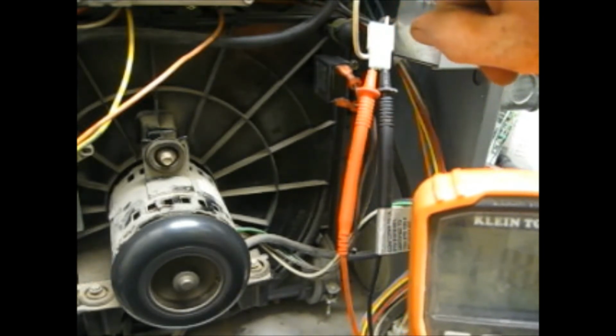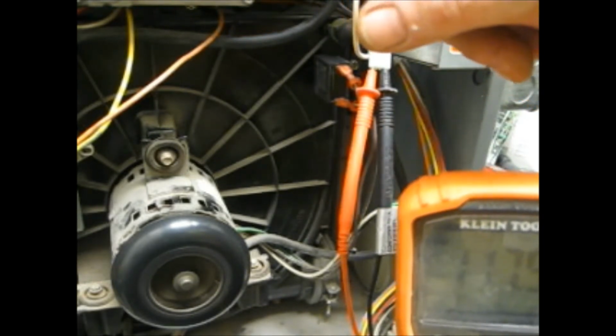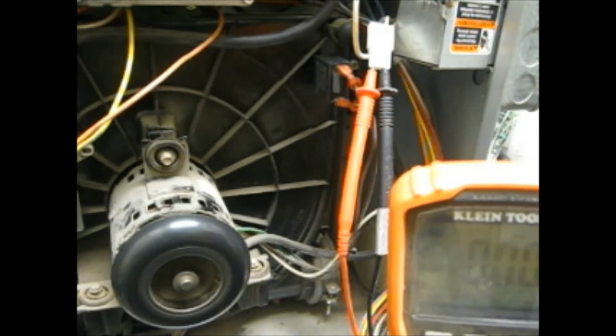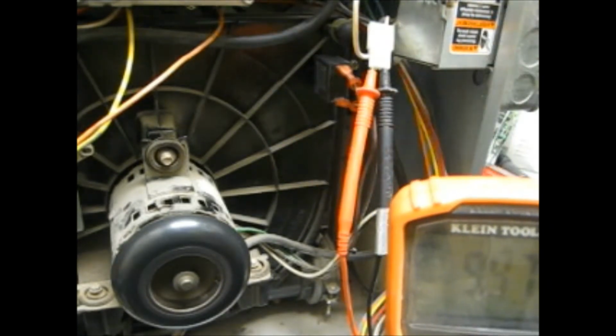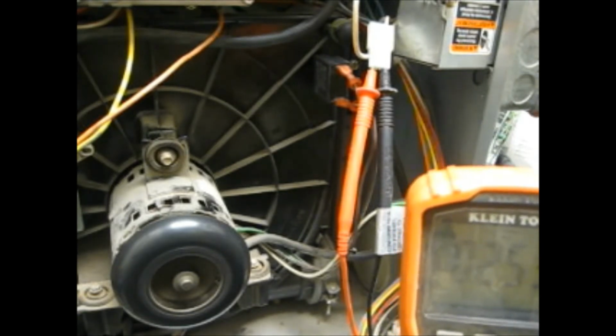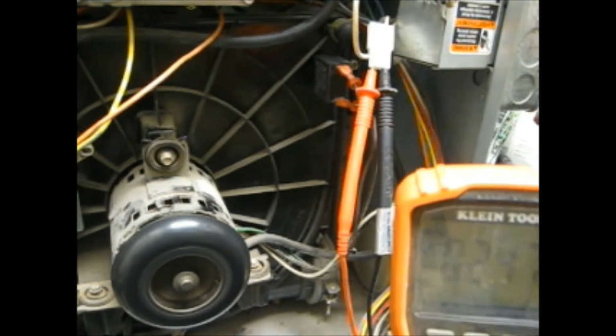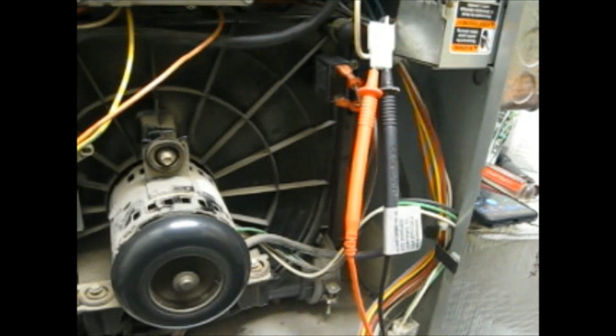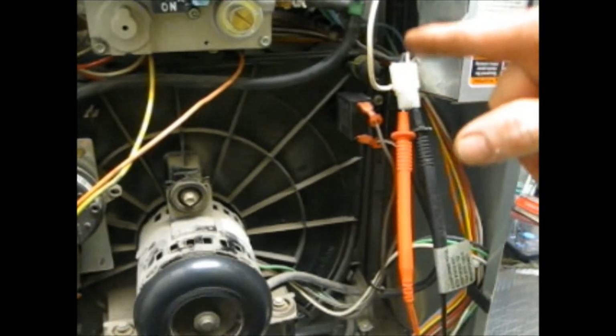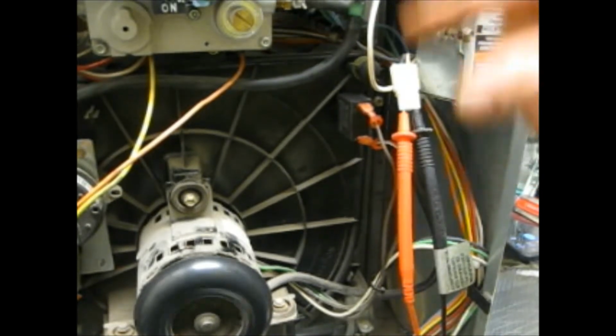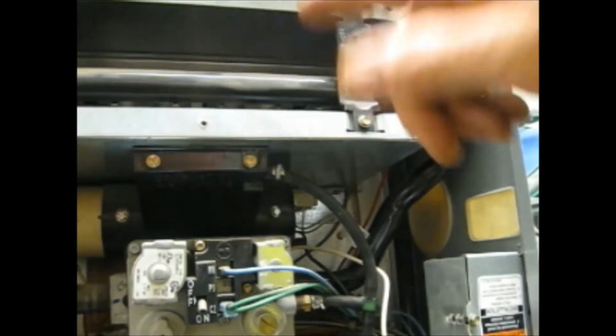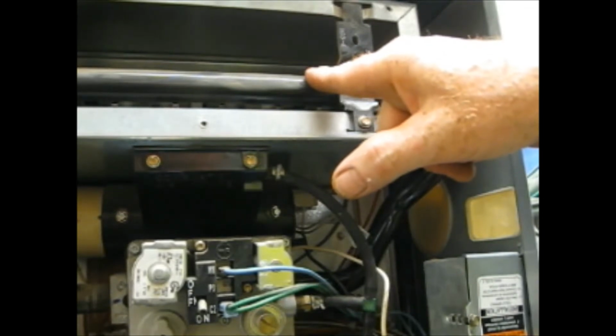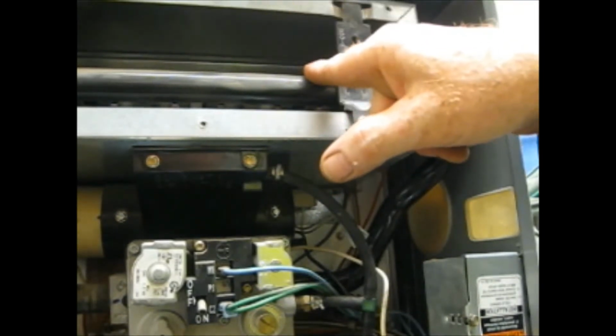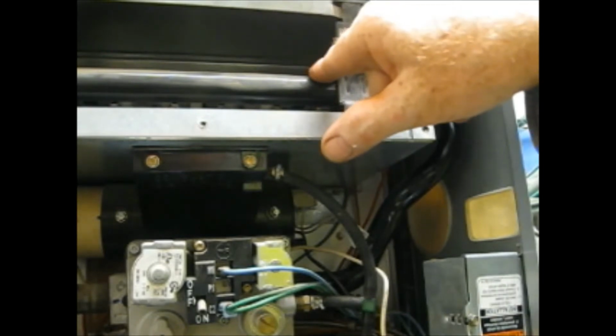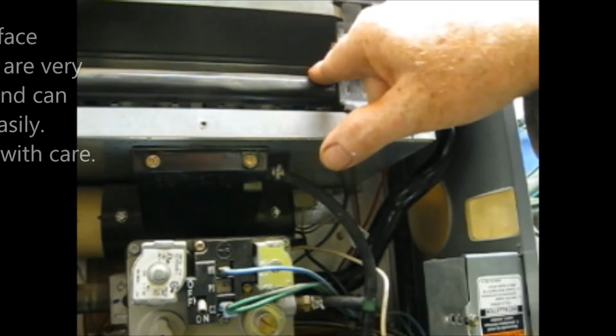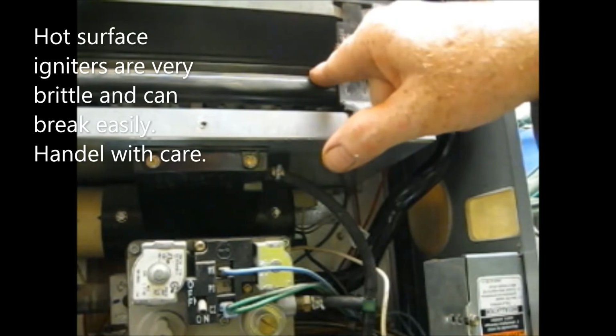the igniter. Now what's going to happen is it's going to attempt to light, but because it's not going to sense any flame, it's going to shut everything down. And there we go. Everything has been shut down because there wasn't a flame up in our chamber. If this were to happen to you where we get 120 volts in our plug up here, but up in the chamber the hot surface igniter is not getting cherry red, there's a good chance that the hot surface igniter is broken or is malfunctioning and needs to be replaced.